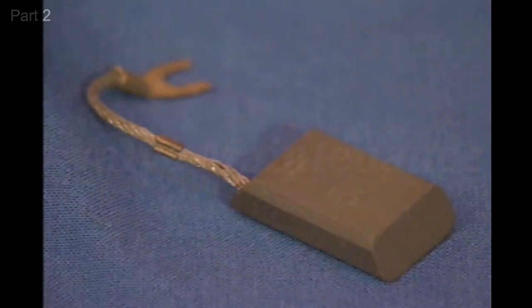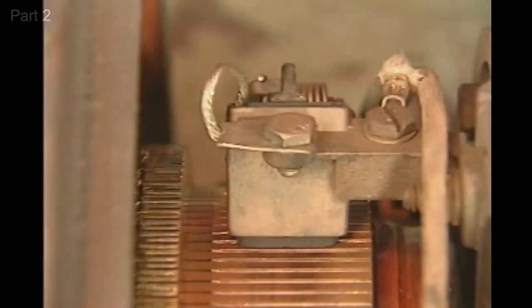Now here's an example of a good brush, one that's not worn or damaged. The surface of the brush is not chipped or cracked, and it is smooth and shiny. The shape of the brush conforms to the shape of the commutator, and the brush is not too short.